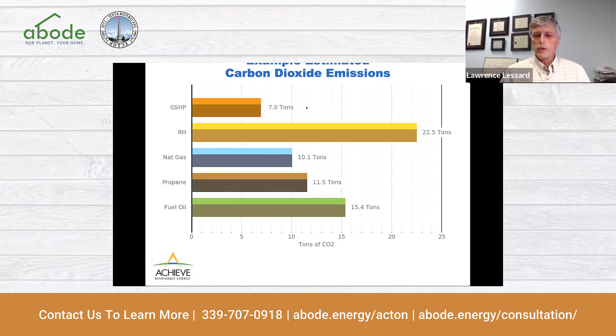So, benefits: the environmentally friendly nature, the high efficiencies of the system, the energy savings. We'll typically see 60 or maybe even 70% savings if someone switches from fuel oil or propane to geothermal. The savings are lower with natural gas because natural gas prices are pretty low right now, but that's changing as the economic recovery happens — gas prices are going up, and probably will go up faster than electric prices, but we'll see.